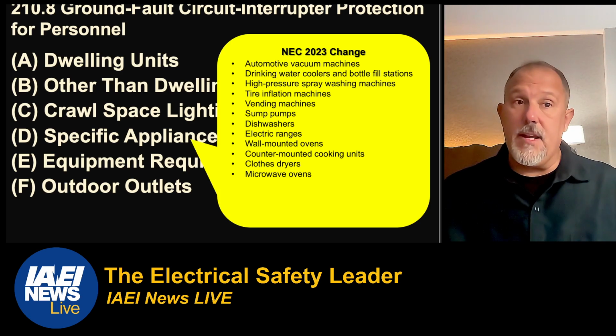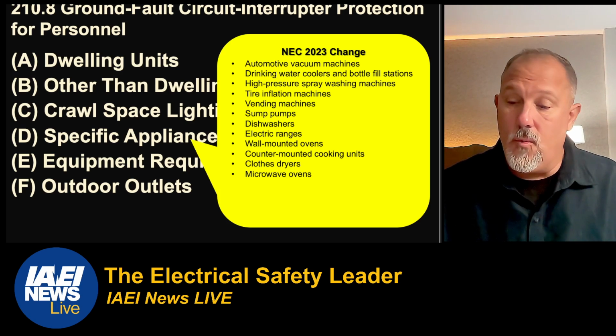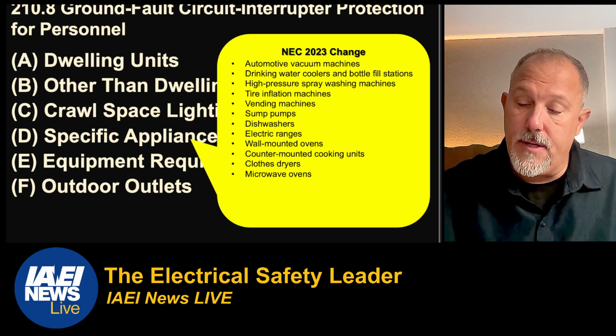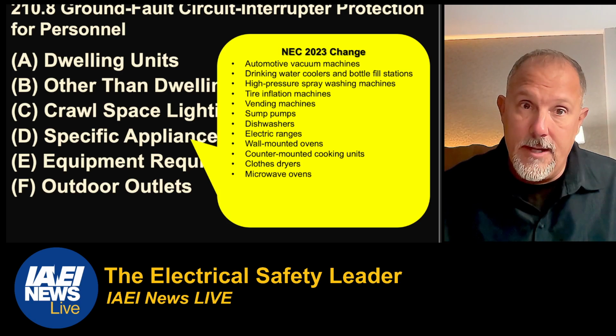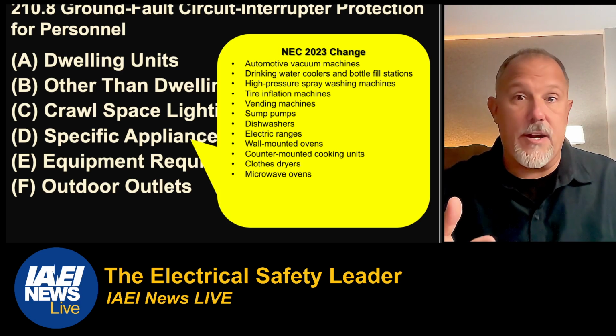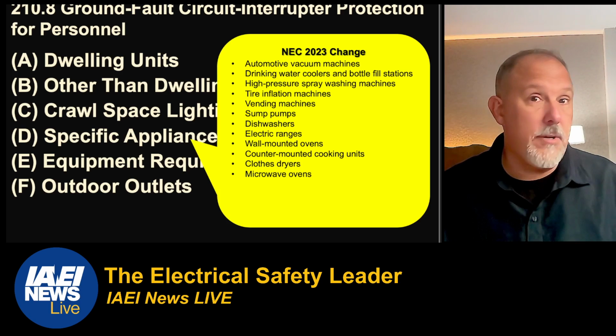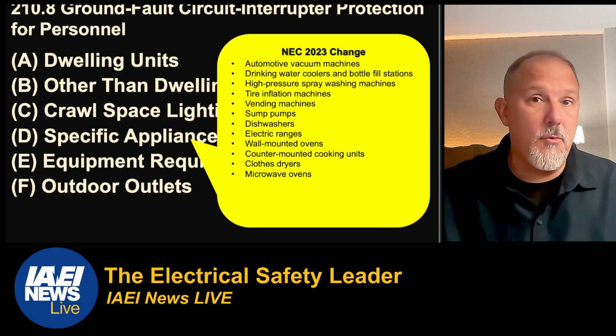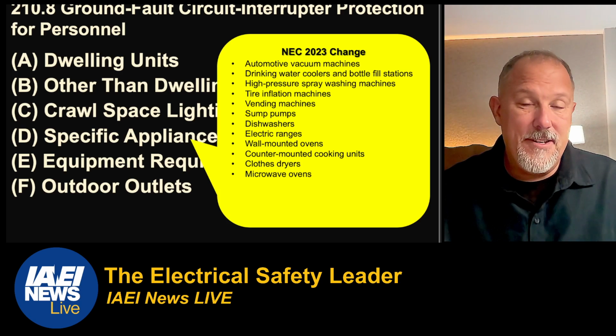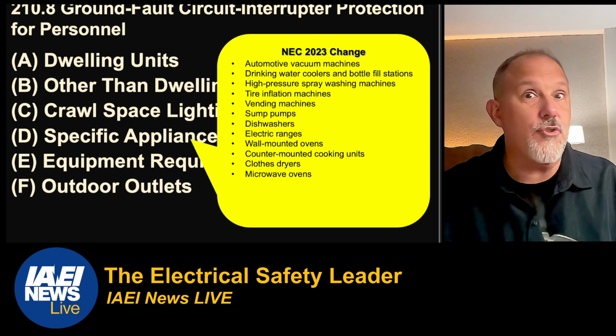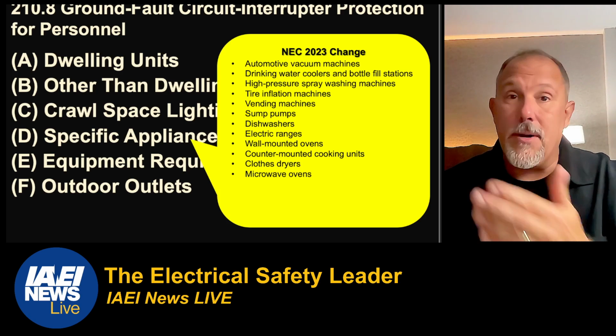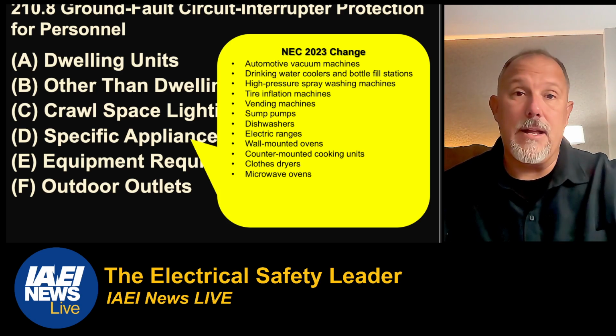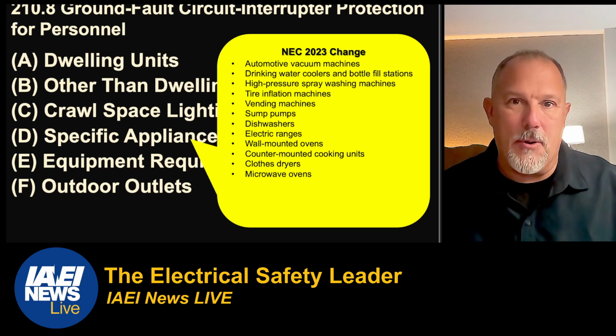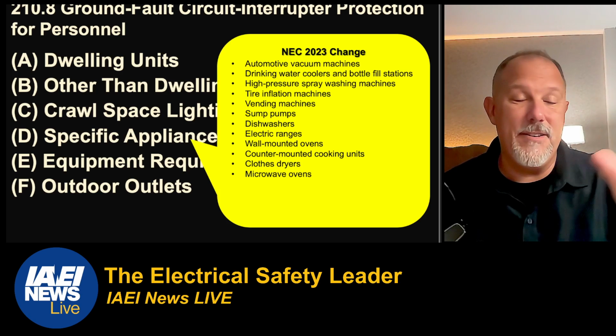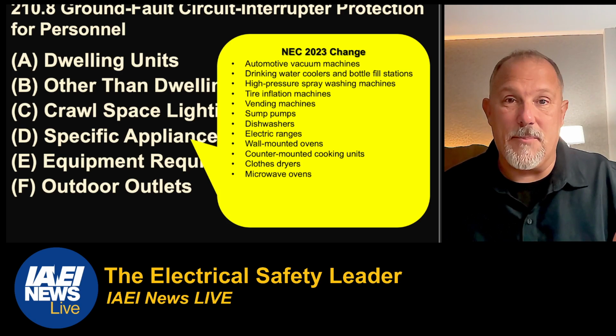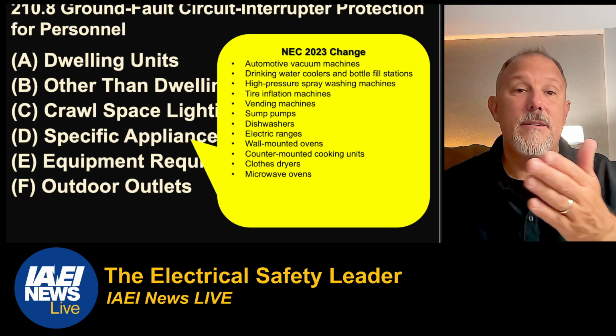In many cases, we had examples of people who were working on these appliances. And if you think about the definition of justified energized work, one of the reasons you can perform energized work is for troubleshooting. When you're trying to fix a microwave or a clothes dryer, you are probably troubleshooting, and you can't turn it off. You can't just unplug it. Or if it's hardwired, you can't turn the circuit breaker off to establish an electrically safe work condition if you need to do testing and figure out why the appliance isn't working. So we had a body count. We had people who were killed. We had qualified people who were working on it and unqualified people. And I'm not even going to entertain the discussion, which you can have somewhere else, of whether the qualified or the unqualified person deserves that protection. We had a number of deaths.